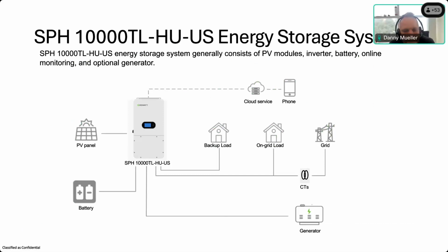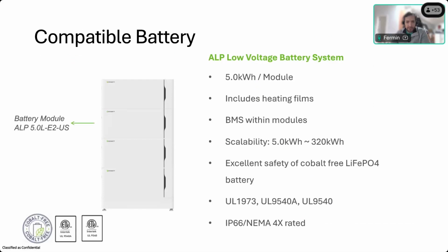Perfect. Sounds good. So this is the compatible battery, which Frankensolar also has. This is our solution for low voltage battery, lithium-ion battery. It's LFP chemistry as well as all of our batteries. In terms of certification, it's certified to UL 9540 with our SPH inverter and UL 1973. It's tested to UL 9540A. This battery comes in 5 kilowatt-hour modules.